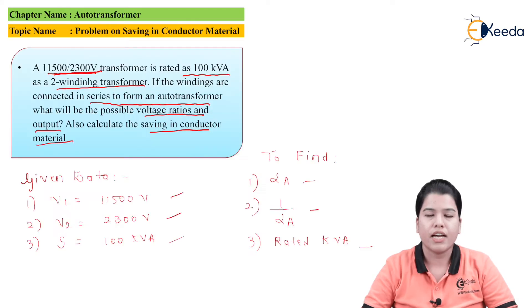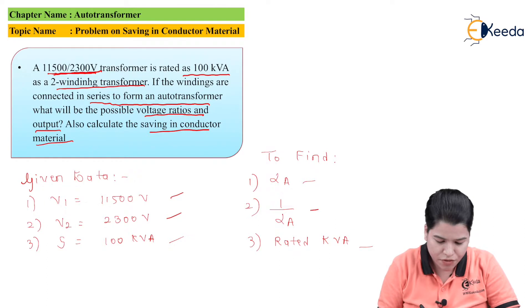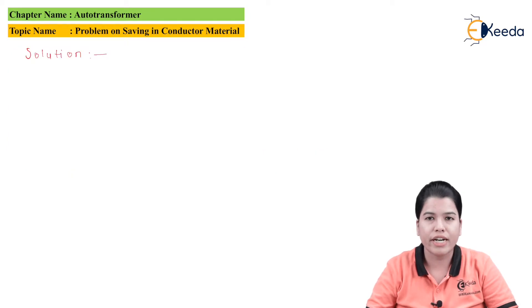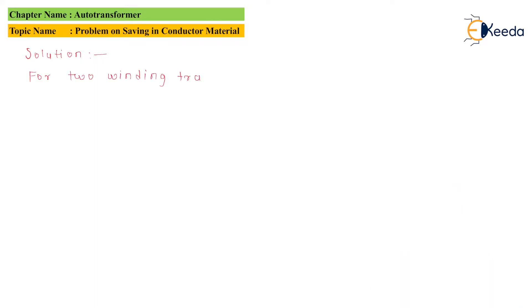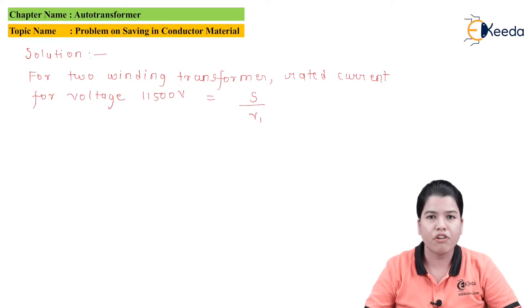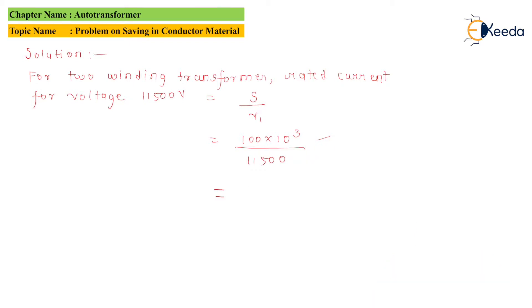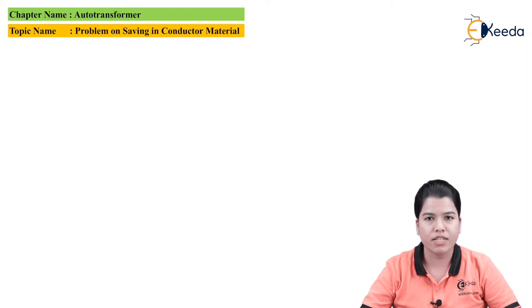The transformer operating 11,500 by 2,300 volt is initially used as the two winding transformer. Let us find the rated primary current. The formula for the primary winding current is I1 is equal to S divided by V1. Substituting the values we get 100 into 10 raised to 3 divided by 11,500, giving I1 equal to 8.69 ampere.